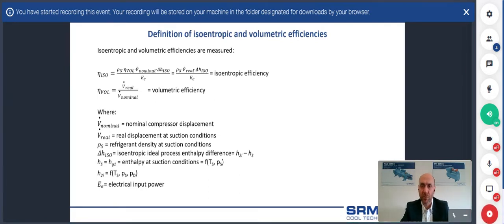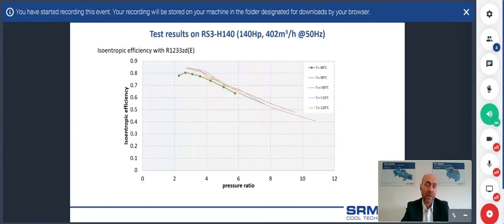But let's go to the test results that we have reached. So first of all, we have a graph that is showing the isentropic efficiency of this compressor testing, that is a series RS3. The size is 140 horsepower. This compressor is indicated with a nominal displacement of 402 cubic meters per hour at 50 hertz. So this graph is showing on the x-axis the pressure ratio, and on the y-axis the isentropic efficiency. This is typical for the screw compressor, having a peak that is very good.